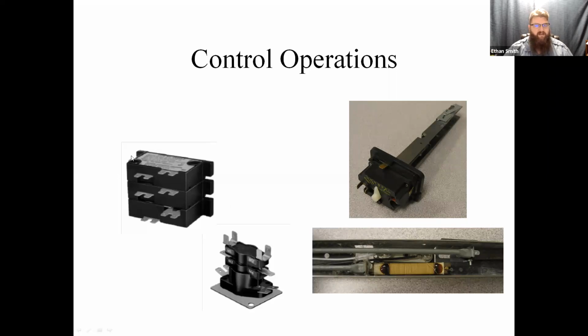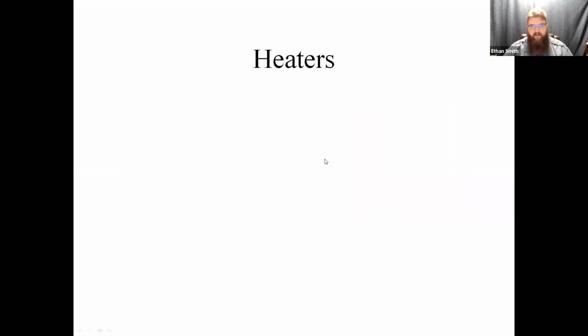These would be what I was referring to in heat sequencers. Time delays sometimes were basically a heat sequencer as well. But we had our source voltage up here, and it had a little heating element. Actually, I take that back. Source voltage was down here, had a little heating element. As that heat propagated through the heat sequencer, it would engage other sets of contacts. So they're everywhere, these little heaters.